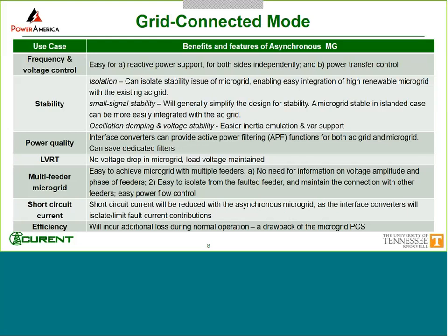It's something I want to explain a little bit, because when you design the microgrid today, if you want to change something, like add some additional PV into it, you would have to redesign the whole thing. But when you have this decoupled link, then that design can be confined to the microgrid itself. Also, for small signal stability, it can simplify the design, like I mentioned, and it can also provide oscillation damping and voltage stability.